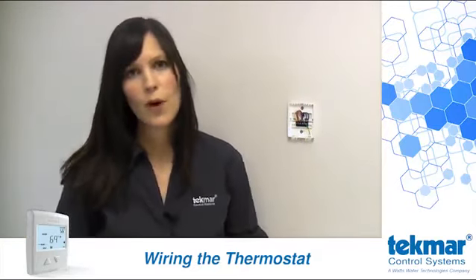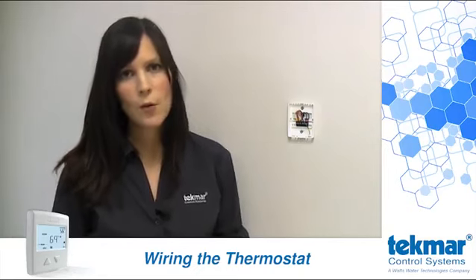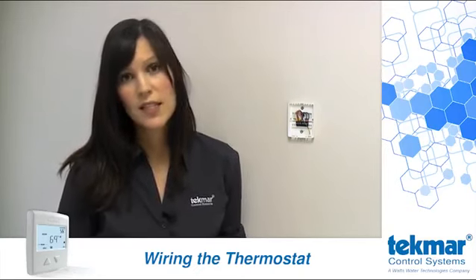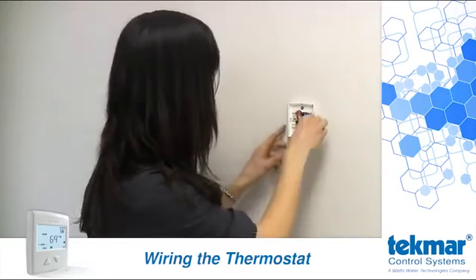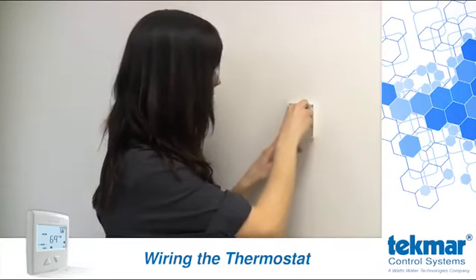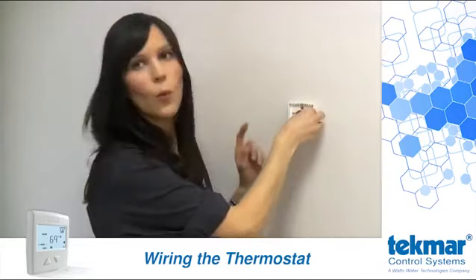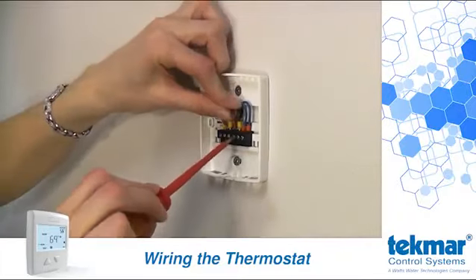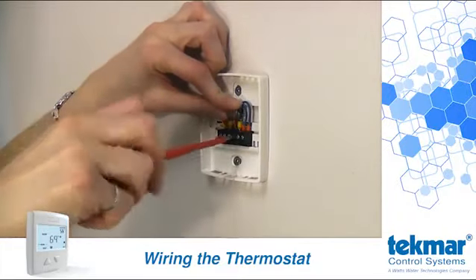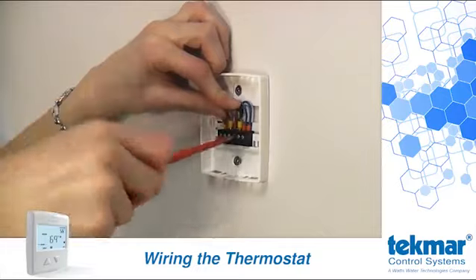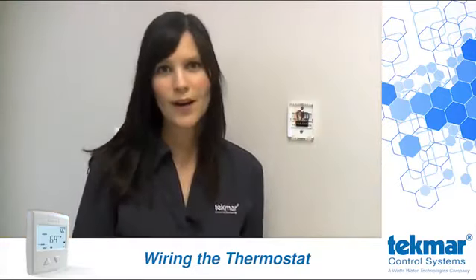Lastly, we're going to bring the wire in from the zone valve. Now, the other wire at the zone valve will go directly to the C on the transformer. The wire from the zone valve will go to the W1 terminal on this thermostat. And we're all wired.